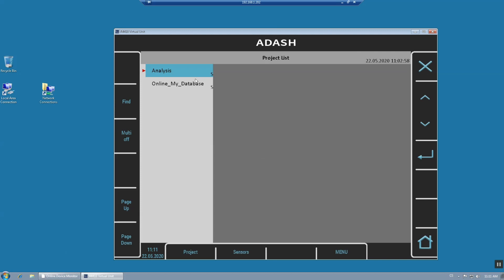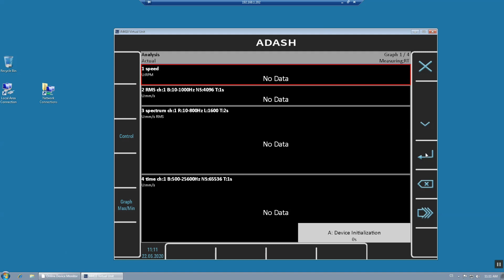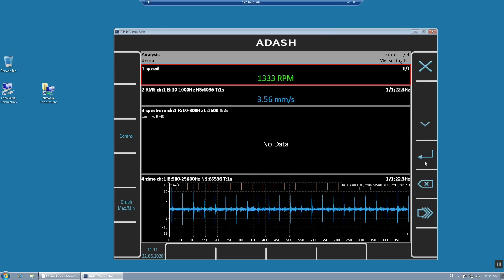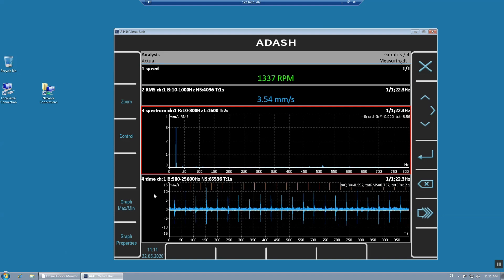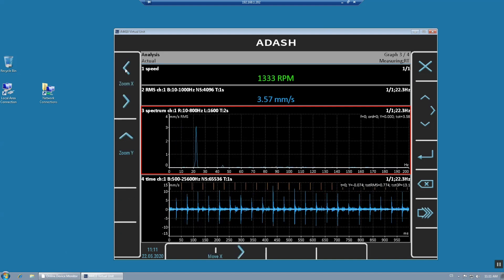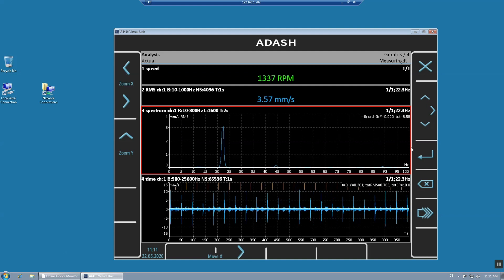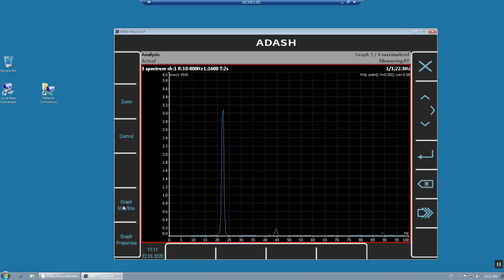It is called the virtual unit and basically it is the same working environment as our portable devices. We can switch off the DDS and connect with the A3800 by remote desktop feature, switch off the online data collection and open the virtual unit. Now we can define the required measurement on the required channel or channels and perform our vibration analysis — overalls, FFTs, time waveforms and so on.